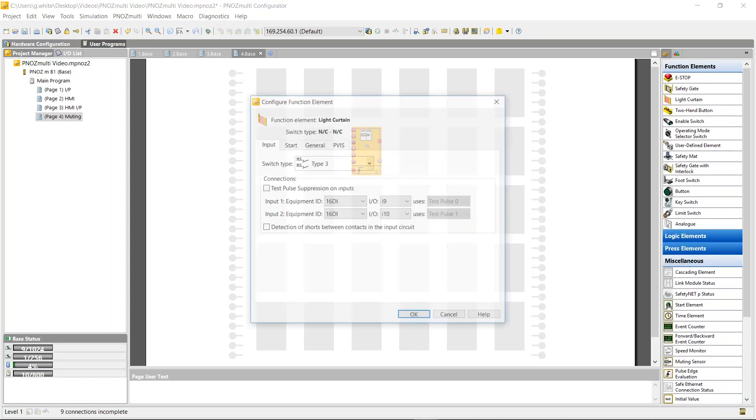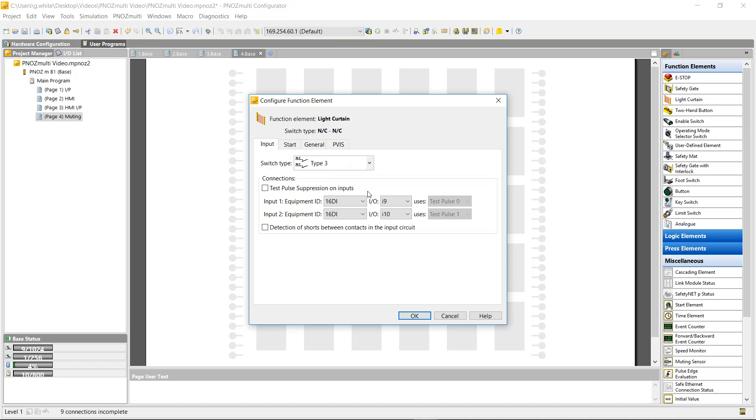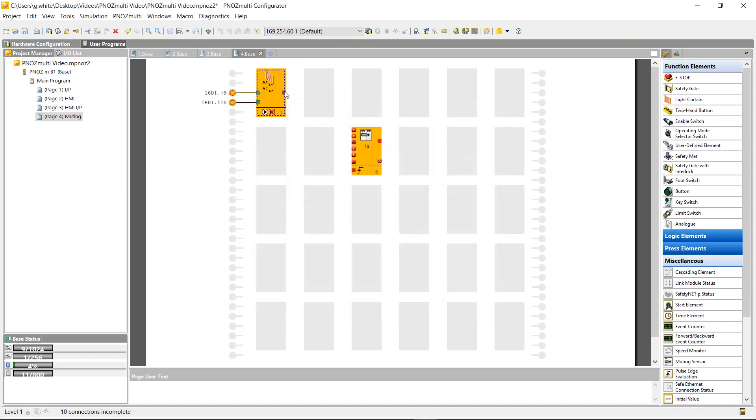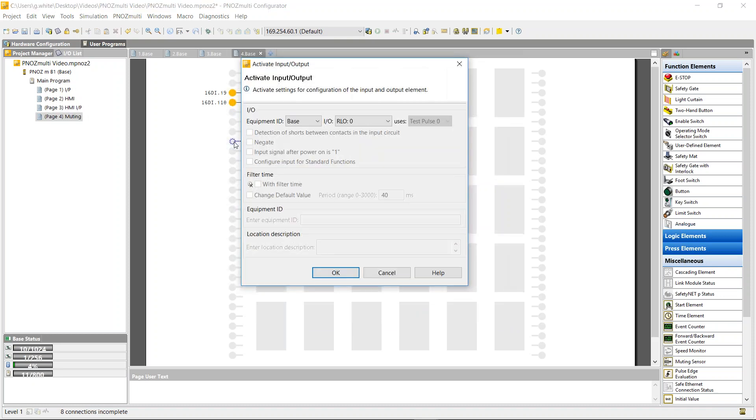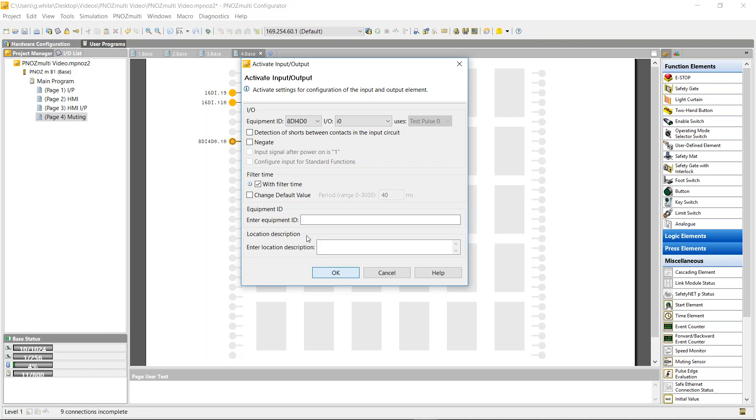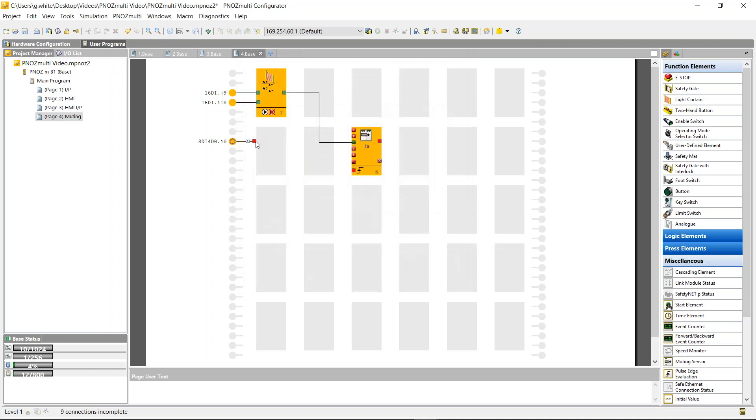Just bring in your light curtain. Normally closed into the 16 digital input. We could also put it into the new 8di4do, but we have a few spare inputs. So we'll just say i9. So this goes here and we're going to introduce four muting sensors now. So we're going to put them into the 8di4do. We're going to say i0. They don't need a test pulse. That's muting sensor one.